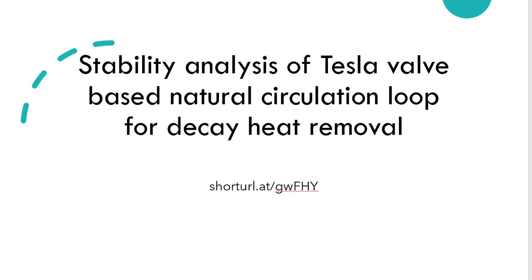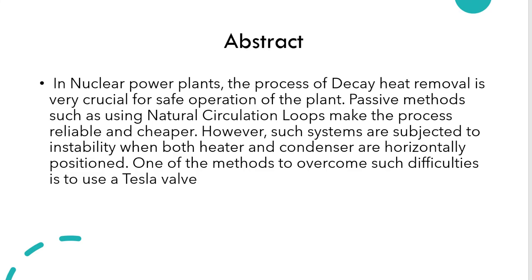Just a general overview: in nuclear power plants, the process of decay heat removal is very crucial for safe operation. Using natural circulation loops makes the process more reliable and cheaper. However, such systems are subjected to instability when both heater and condenser are horizontally positioned. One of the methods to overcome such difficulties is to use a Tesla valve.